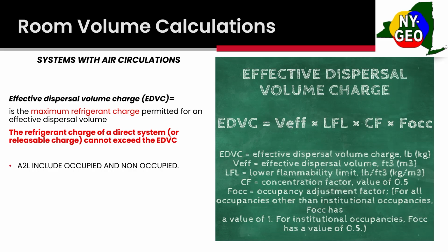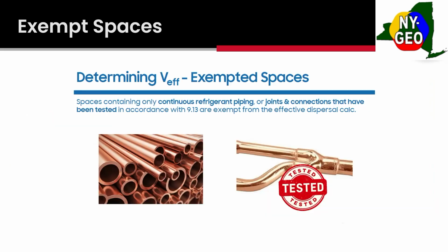So for your EDVC, the first thing you've got to do is figure out your effective dispersal volume. That's the area the unit is serving. So it's either this conference room, or a bedroom. You've got to figure out your volume and your lower flammability limit. As I mentioned, you get that from ASHRAE 34. Then you're going to multiply that by a concentration of 0.5. That is a set value. And then depending on your occupancy, it's either going to be commercial or institutional. If it is institutional, we cut it in half, so it's multiplied by a factor of 0.5. So that's the real high-level overview of your EDVC, but that is the biggest change going from A1 to A2L when you're designing with refrigerants. There is one big exemption in here, which I really appreciate.